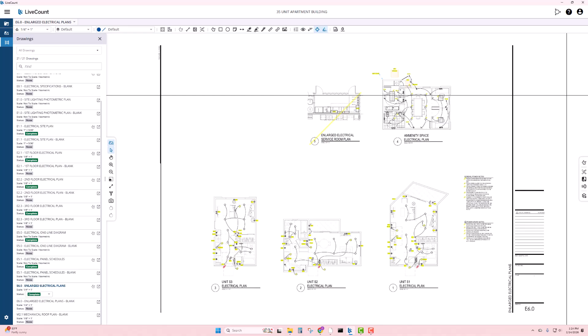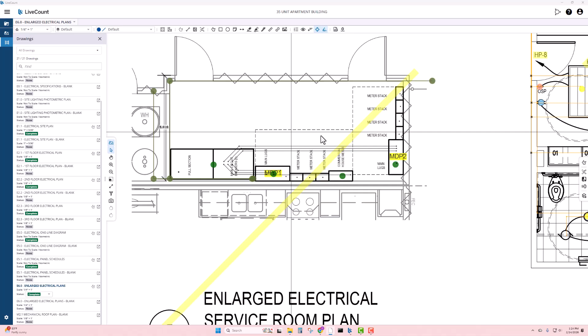Then what I did to make things fast, I went to the enlarged electrical drawings. I did all the feeders here on this drawing in copper. So the service entrance cable going out to feed the MDP1 and MDP2, you can see in copper. And then as far as aluminum feeders go, what I did was I sized them and then I copied everything over and then I substituted the items appropriately. So you can see here we have an alternate cost for aluminum feeders. You go from copper to aluminum. So it'll be the same runs, same lengths and everything like that, just different cable. And that takes care of feeders.